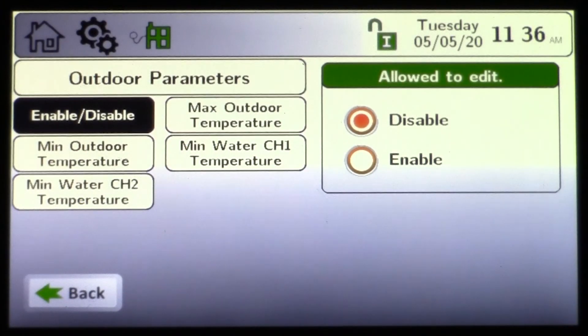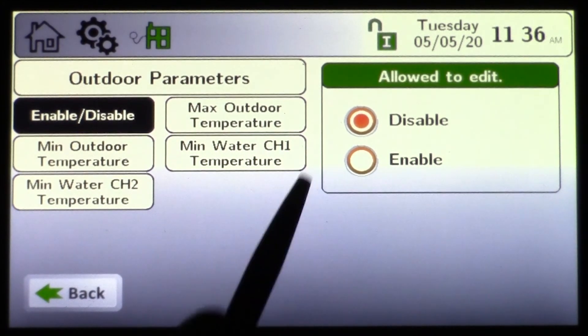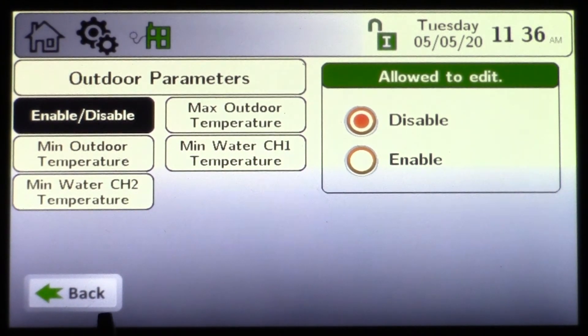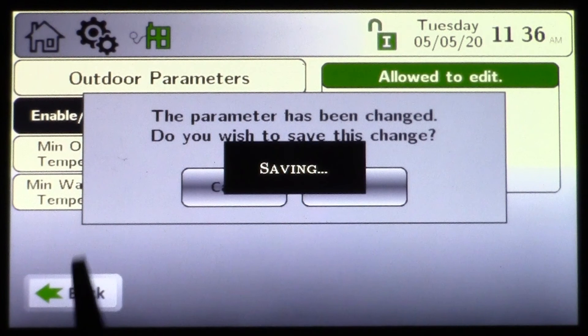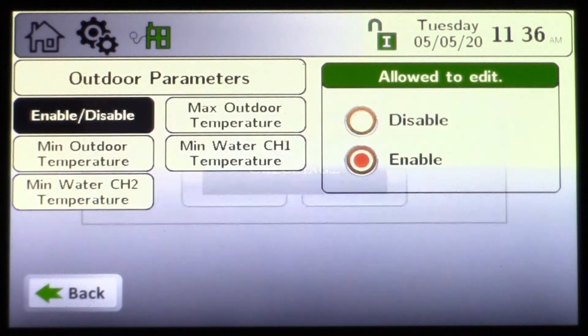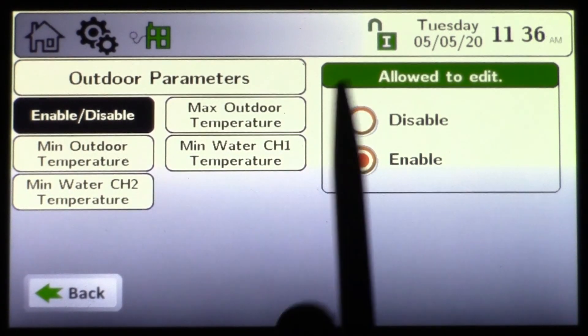Outdoor reset can be enabled or disabled. Why would you ever disable it? If energy management is controlling the outdoor reset, that's where you'd come in and disable it. It's currently disabled from the factory. If you have an outdoor sensor and you're doing outdoor reset, you need to enable it — and it will not allow you to enable if you're not in the installer icon.